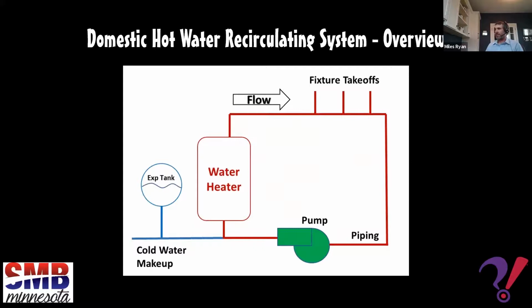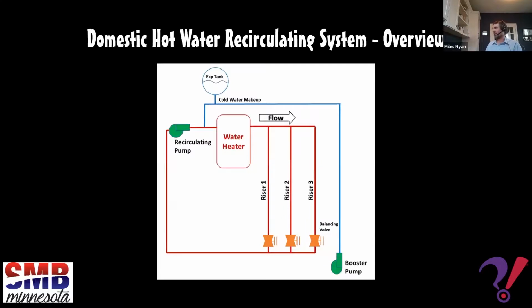Now, if you have something as simple as this, you probably don't have many issues with it. And probably as TAB professionals, you probably never looked at something this simple, right? But once you start getting into the high-rise residential units and other high-rise buildings, there might be multiple paths for the domestic hot water to flow through, right? So from each one of these 3 risers here, you want to have hot water constantly circulating through each of these 3 risers because they all have respective takeoffs going to different fixtures serving different units within that facility.